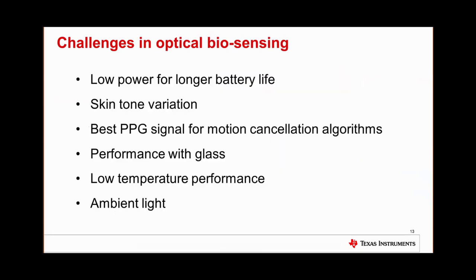For optical biosensing challenges: apart from battery life, PPG measurement uses an LED for transmitting light and a photodiode for receiving the reflected signal. The patient's skin tone variation can really affect the received signal — its amplitude is highly dependent on skin color. Combining LED and photodiode in a small form factor requires attention to glass and lens performance, along with cancellation of ambient light and software correction. Many wearable monitors also have motion cancellation algorithms to compensate for motion artifacts.